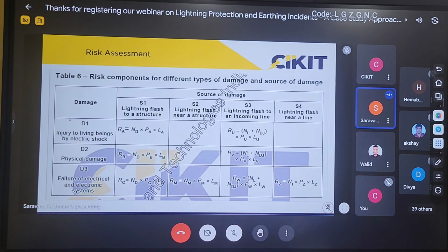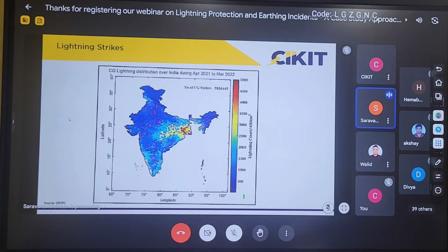So as I mentioned, one of the most important parameters on which the risk assessment value mainly depends is the number of thunderstorm days. In this map, you can observe that they have marked the number of lightning strikes in different regions. If you closely observe, the regions on the right side, West Bengal, Odisha, Bihar, Patna and Uttar Pradesh, receive more lightning strikes in India. So if I am working on certain kinds of locations, then I have to take more preventive actions for reducing the loss due to lightning.